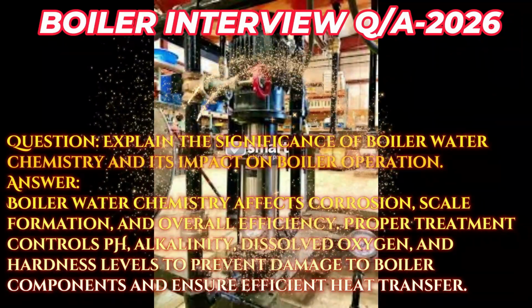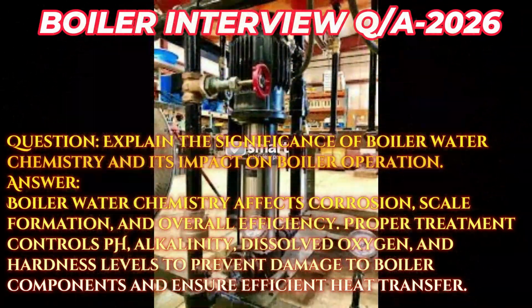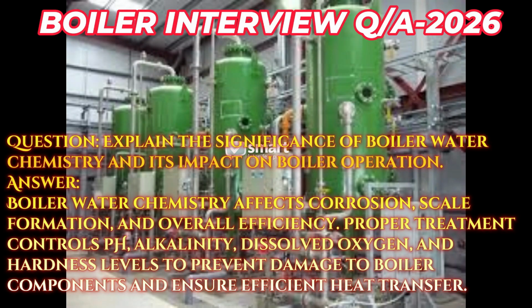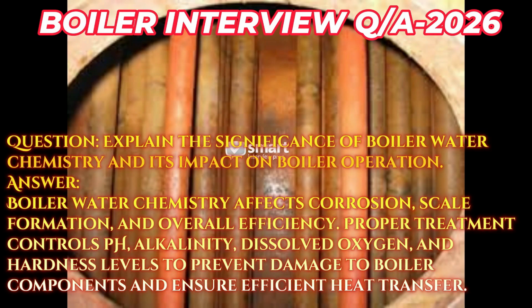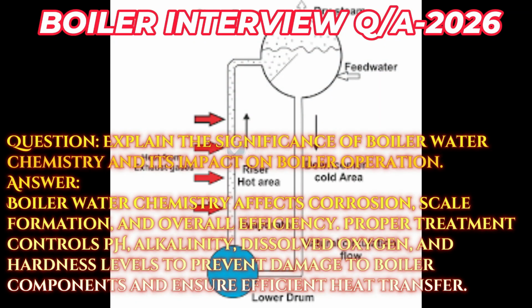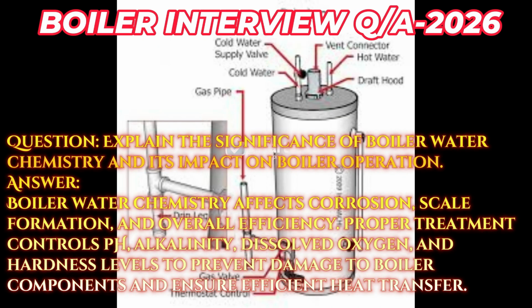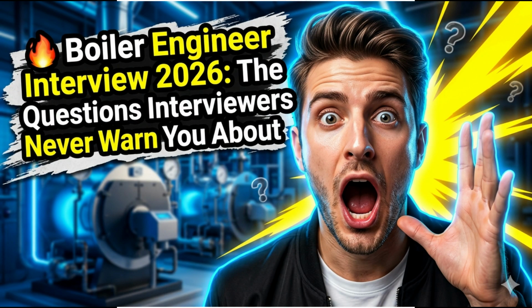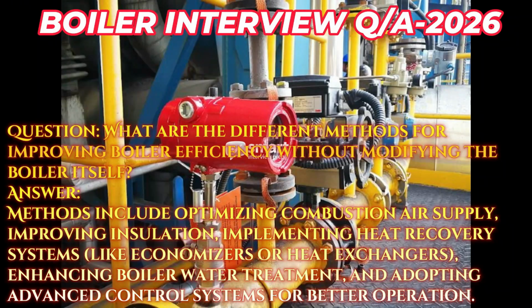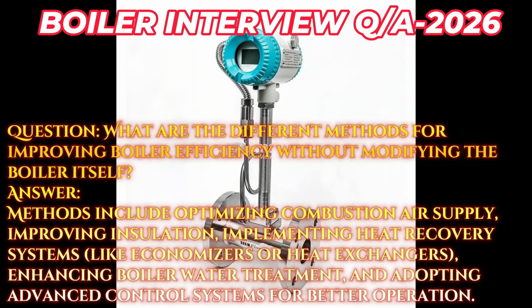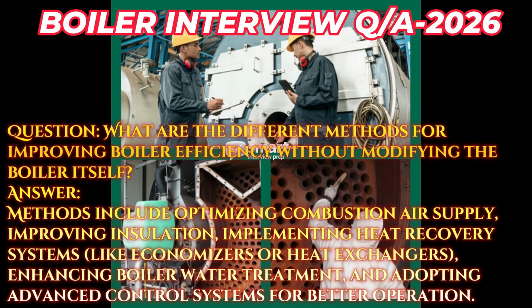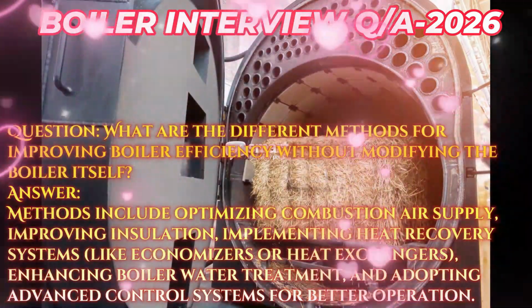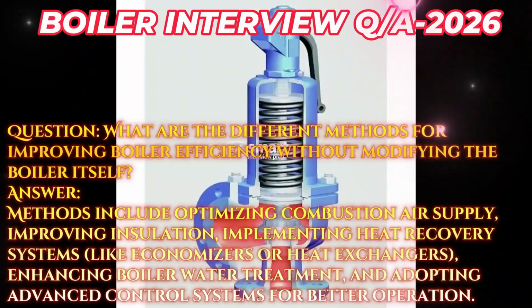Question: explain the significance of boiler water chemistry and its impact on boiler operation. Answer: boiler water chemistry affects corrosion, scale formation, and overall efficiency. Proper treatment controls pH, alkalinity, dissolved oxygen, and hardness levels to prevent damage to boiler components and ensure efficient heat transfer. Question: what are the different methods for improving boiler efficiency without modifying the boiler itself? Answer: methods include optimizing combustion air supply, improving insulation, implementing heat recovery systems like economizers or heat exchangers, enhancing boiler water treatment, and adopting advanced control systems for better operation.